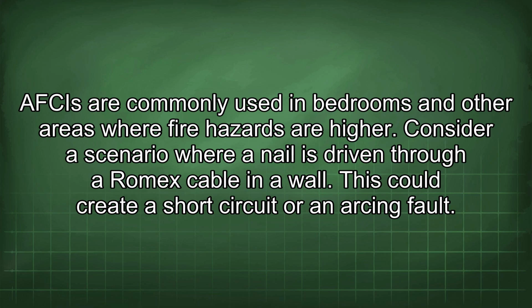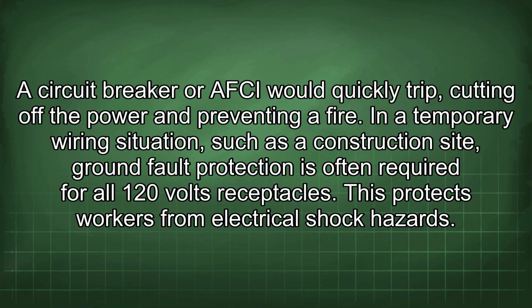Consider a scenario where a nail is driven through a Romex cable in a wall. This could create a short circuit or an arcing fault. A circuit breaker or a fuse would quickly trip, cutting off the power and preventing a fire. In a temporary wiring situation, such as a construction site, ground fault protection is often required for all 120 volts receptacles. This protects workers from electrical shock hazards.